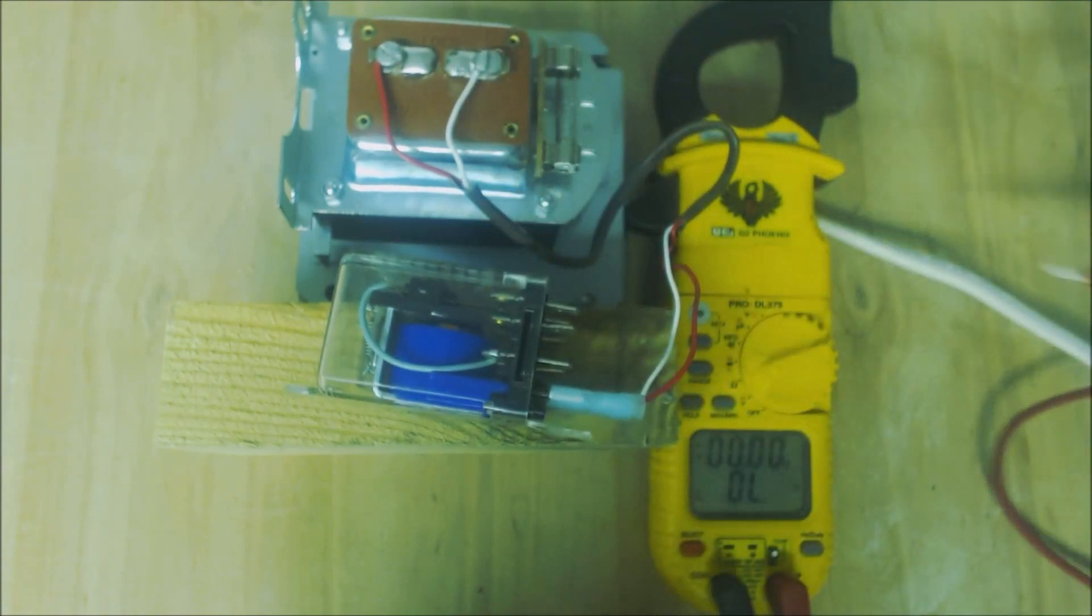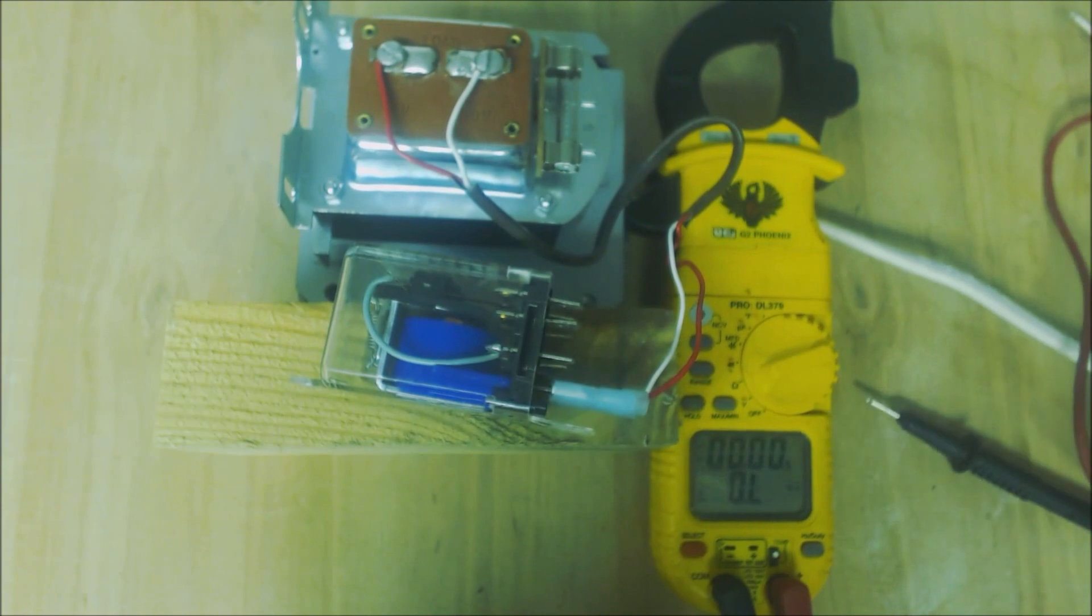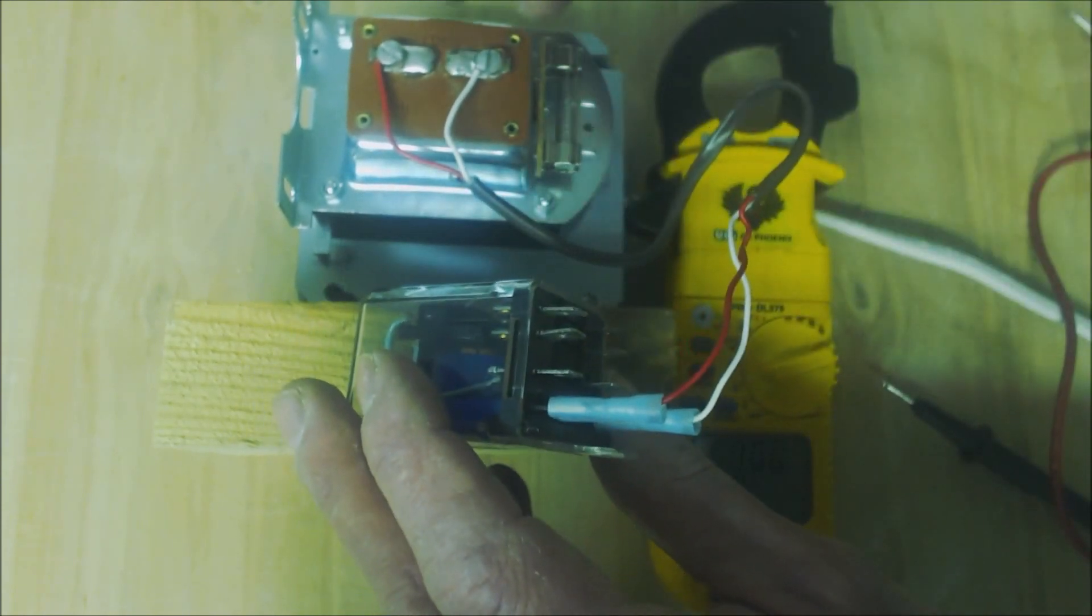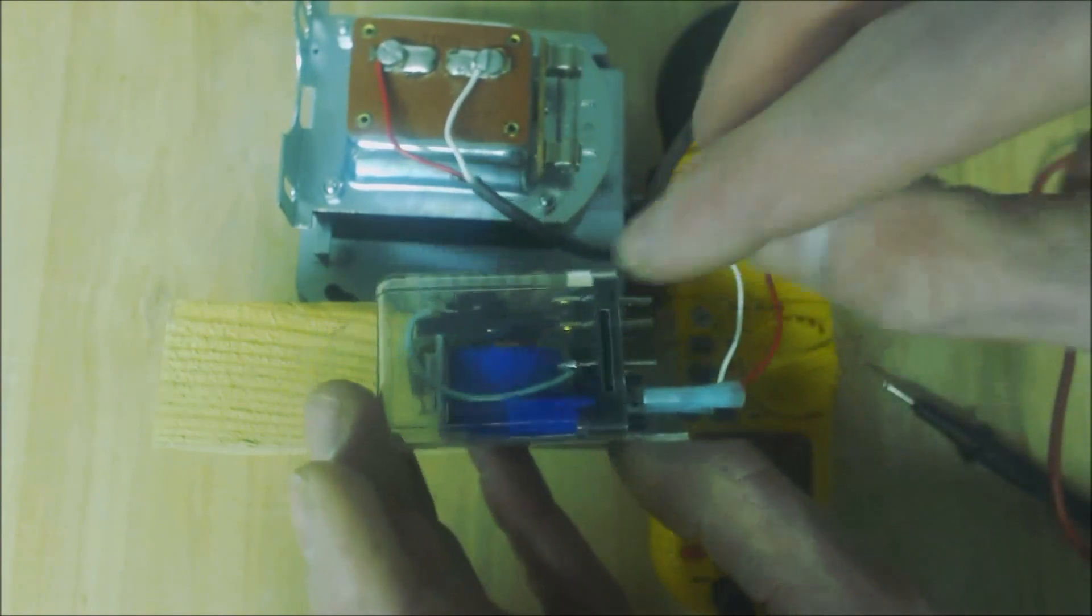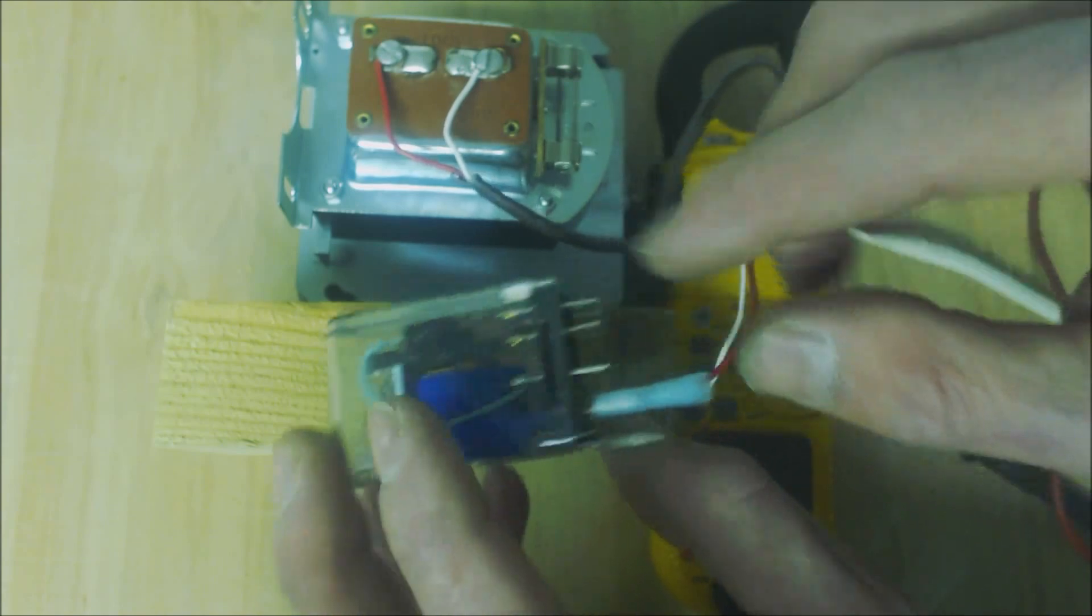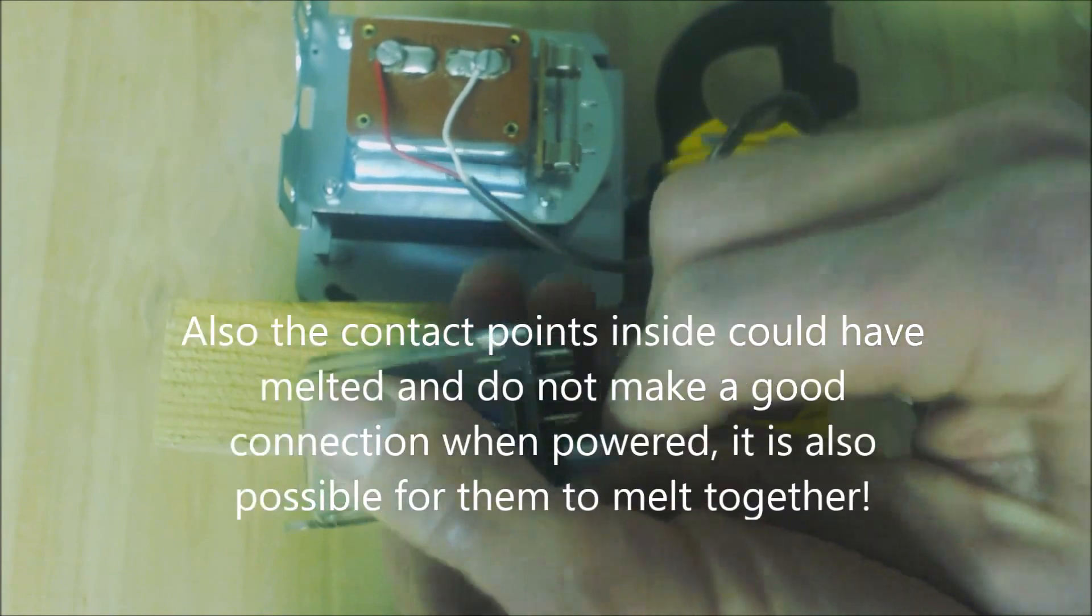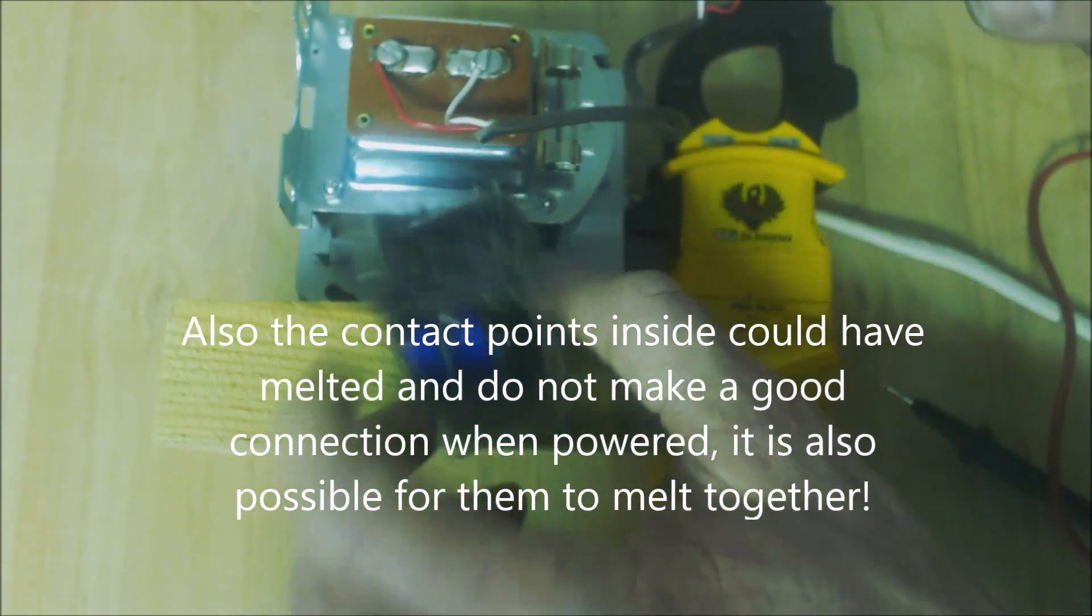That's how it works. Same thing happens on both sides. I'm going to turn the power off for a sec. Now the power is off to the transformer coming over to here. If you do not see this coming down and touching this contact right here, then it's likely that the coil is bad. I'm going to unplug it and show you how to test resistance on these.